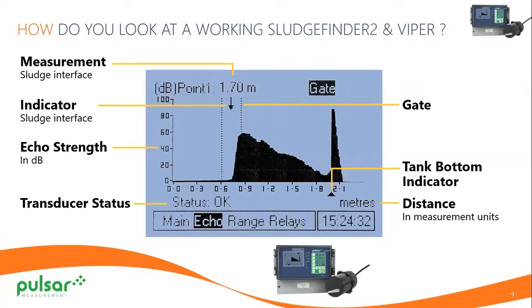And then you have on the left-hand side your echo strength in dB. At the bottom, you have your transducer status, which is saying okay. And the gate, which surrounds your indicator, which locates the level. And then to the right, we have our distance in measurement units, and that's set up earlier in global in the scroll down menu. And then we have the tank bottom. This is what you would see on a standard Sludge Finder 2 and Viper controller. You can also view this on PC Suite.